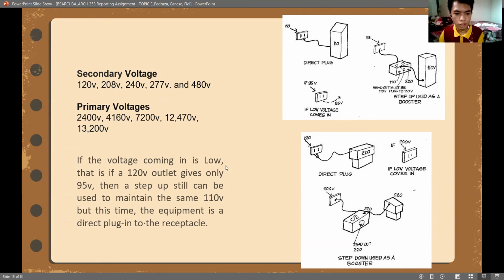If the voltage coming in is low, that is, if a 120 volts outlet gives only 95 volts, then a step up can still be used to maintain the same 110 volts, but this time the equipment is a direct plug into the receptacle. So we are going to use the step up this time because the outlet only gives 95 volts. In order to give the exact voltage, we're going to use the step up through the direct plug into the receptacle, as you can see here.